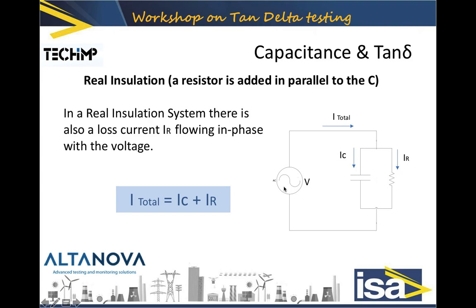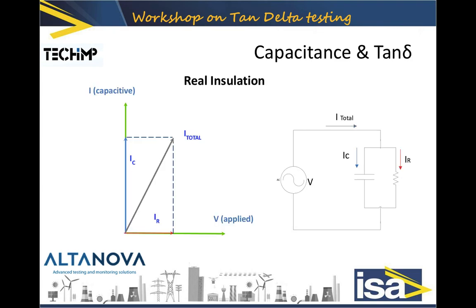Since capacitive and resistive currents are shifted 90 degrees in phase, we use a vectorial sum. We drew IR much larger than it usually is — realistically it would be only a few millimeters on this drawing — in order to make it easier to understand. The resistive current is in phase with the voltage, while the capacitive current leads by 90 degrees. This is how currents and voltages are represented in a real insulation.